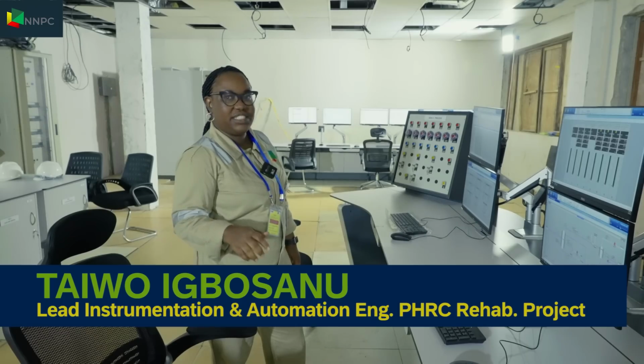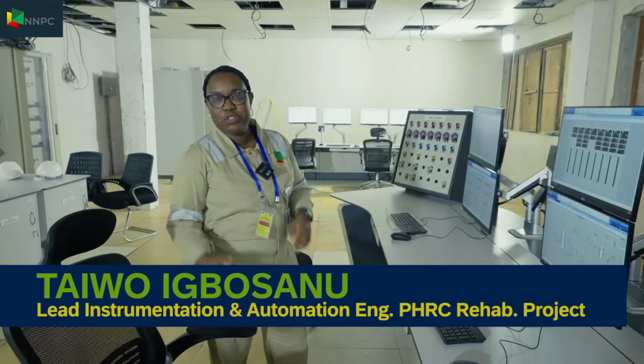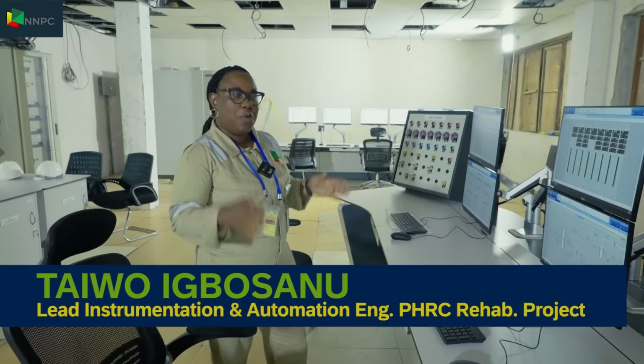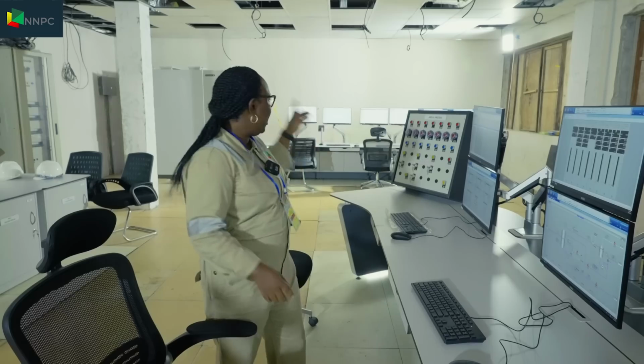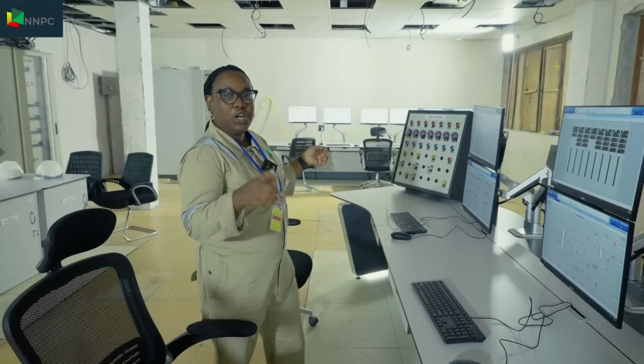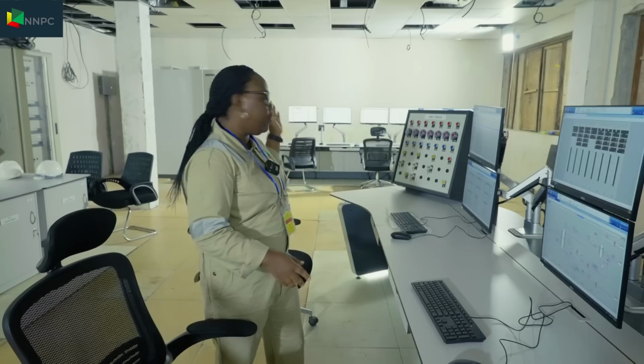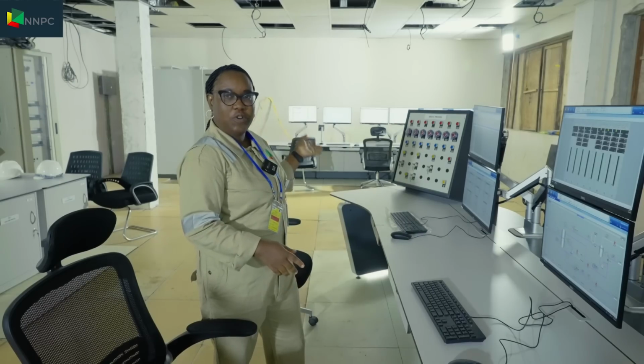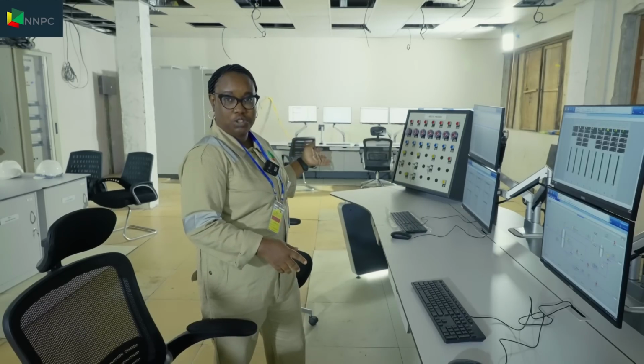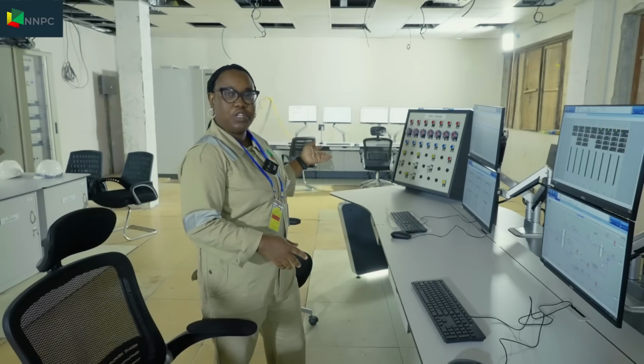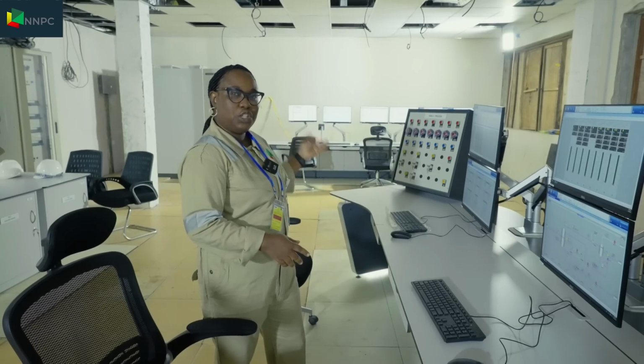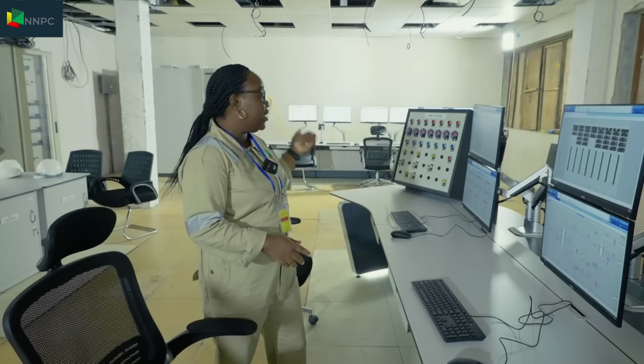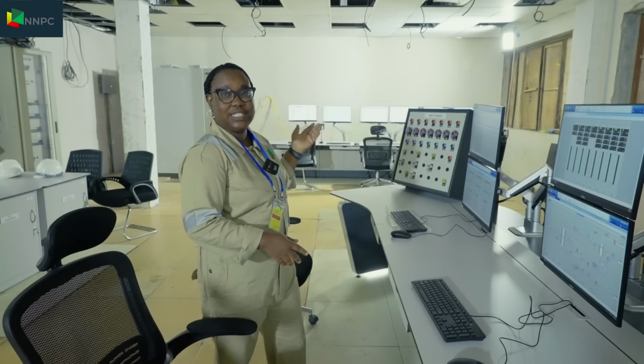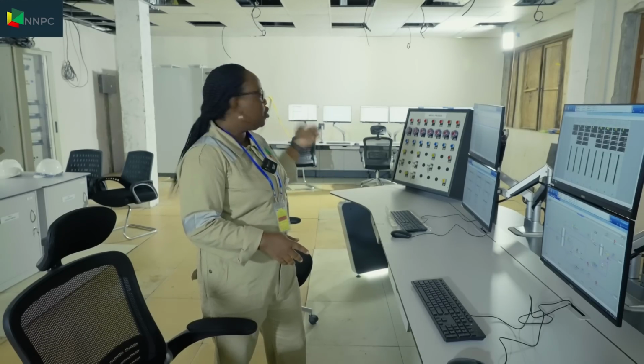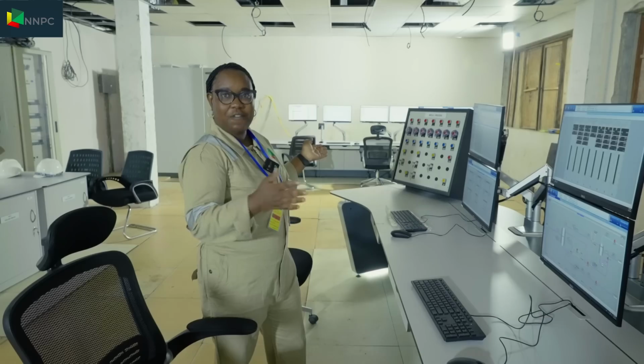So in here is the control room. The cables from the rack room come into here. We have the operator's workstation, and then we have the engineering workstation. The operator workstation is 5, the engineering workstation is 4. The engineering workstation, one of them is for the distributed control system. The second one is for the ESD, that's the emergency shutdown fire and gas system. The third one is for plant resource management, and the fourth one is PIMS, that is plant information management system. So we expect to have 4 engineers and 5 operators.